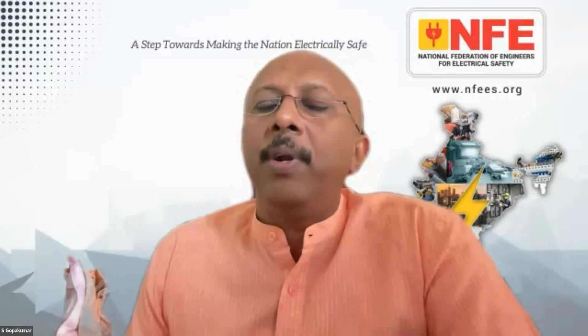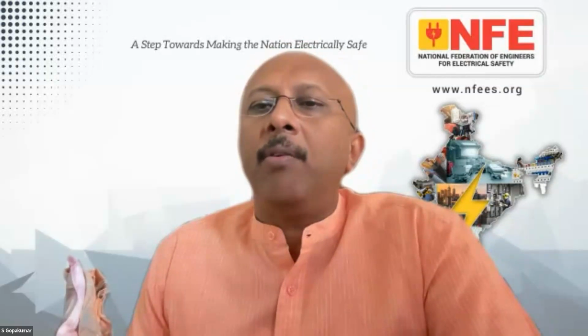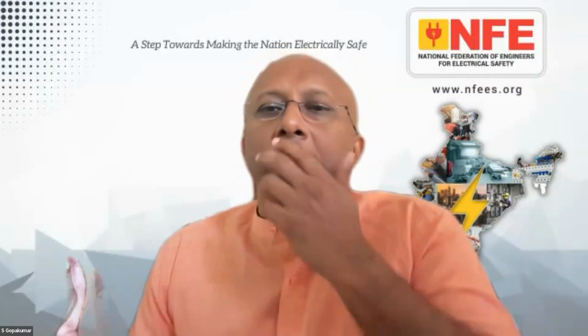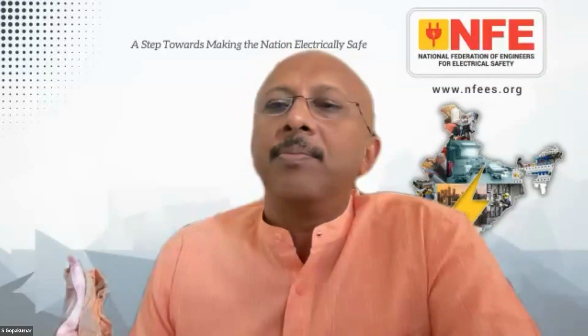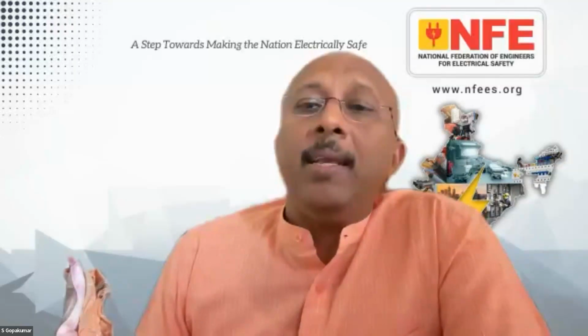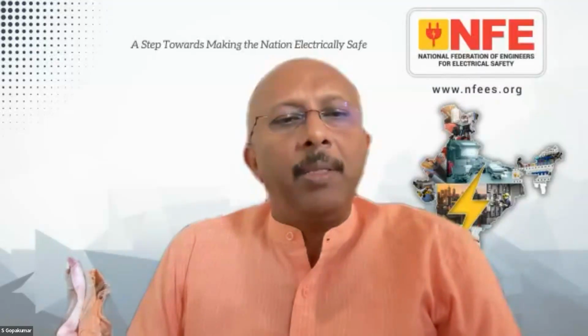So who will provide the RCD for the elevator? The main power and car manufacturer or the client? Of course, sir, would you like to answer this, Vishnu sir? Who will provide the RCD for elevators? It is provided by the customers, and generally provided in the main distribution panel. Coming to the car lighting, car lighting also comes from the distribution panel, and many companies do have provision of single-phase RCDs within the controller, but it's generally provided by the customer in the main distribution panel. That means the customer will give a separate three-phase supply and a separate single-phase supply? In the same distribution panel, yes.